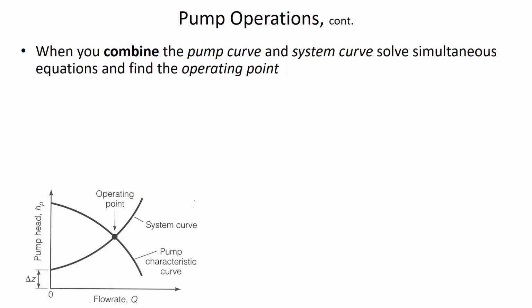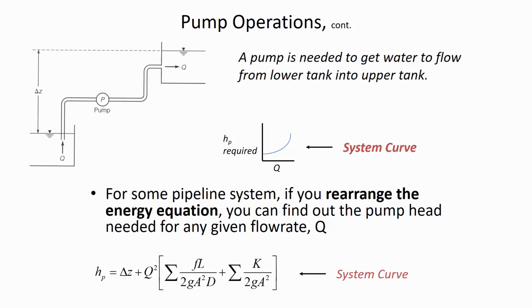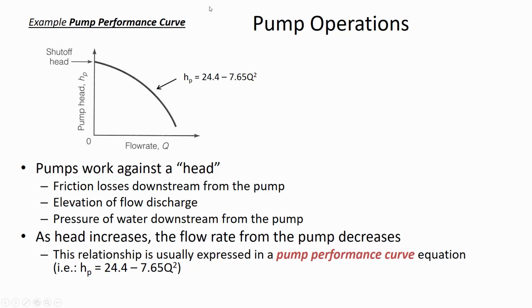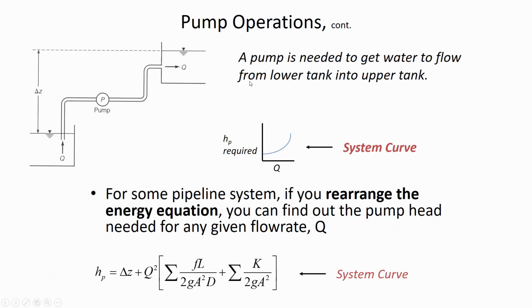All right, so here are these 2 graphs. We've got the pump curve down, the system curve up, and what flow rate actually is there when you combine a certain pump with a certain system. It's when you graph them together and the 2 curves overlap. That's what we call the operating point. And essentially, that's the graphical solution. The paper solution is you're setting HP equal to HP, because both of these equations, here's our typical pump equation, it's in terms of HP and Q, right? So is the system curve, HP in terms of Q.